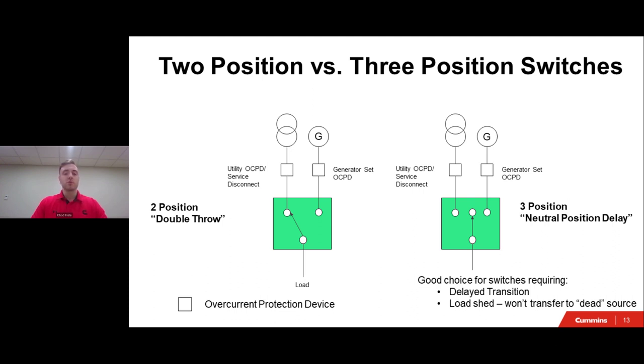The difference between these two switches is that the three position switch, which is off to the right there, is designed with a center off position. And you can see that displayed in the diagram. You have those three dots. On the left would be your normal source, and then on the far right is your emergency source. But in the middle there, there's that center dot, and that is what is known as your center off position or your neutral position. This allows for the switch to be disconnected from both sources of power.